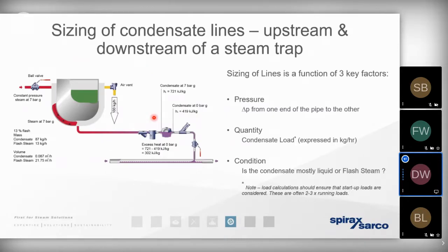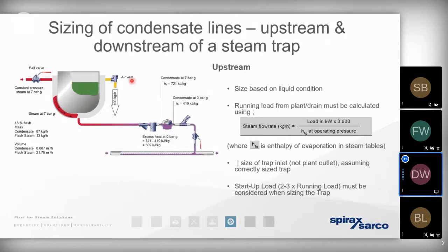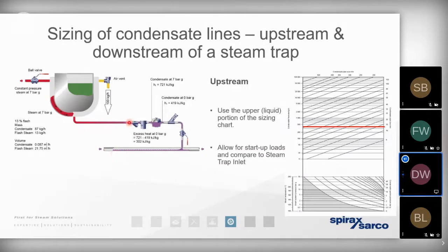So just moving on to the pipework sizing, we've mentioned upstream of the trap, the condensate at this point here is a liquid, it's under pressure. So as long as we've allowed for that safety factor, as long as we've multiplied the condensate load by 2 to 3 times the running load, for example, then it's safe for us to move forward and size the pipework at this point here, assuming that we're moving water. We can use water sizing charts, as is demonstrated over here, towards the right-hand side of the screen. We can even use the calculators or configurators that we have on those useful little apps.